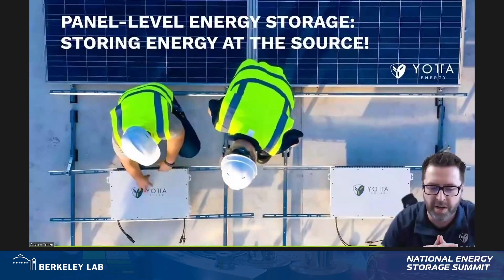As you can see on the rooftop here, our battery installs beneath the solar module directly at its source of generation. What enables this technology is a phase change heat exchange thermal management approach, which is entirely passive. There are three key components: a layer of ceramic material that provides insulation and also doubles as fire protection; a mass of phase change material which absorbs energy once the temperature internally gets to 100 degrees Fahrenheit; and thirdly, a heat exchanger that rejects energy to the environment overnight, regenerating the phase change material and allowing the product to cool down to 70 degrees Fahrenheit.